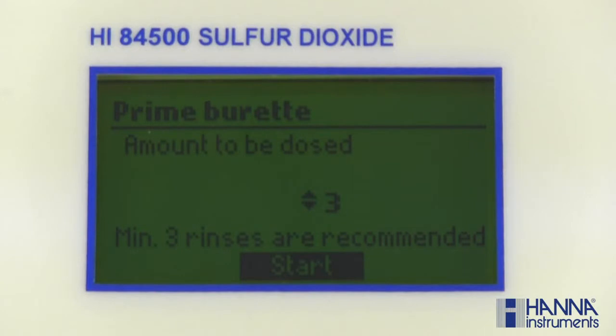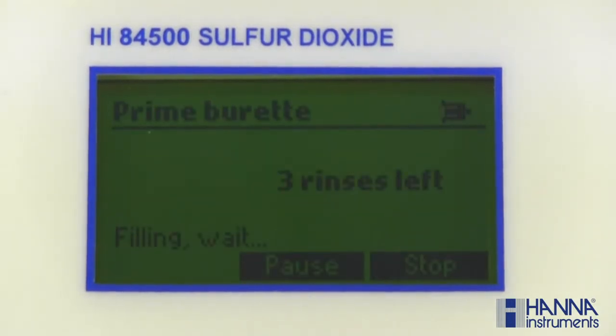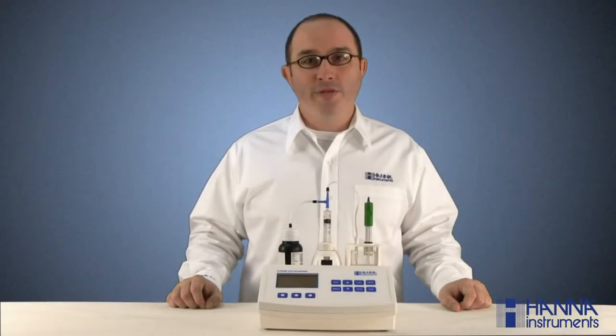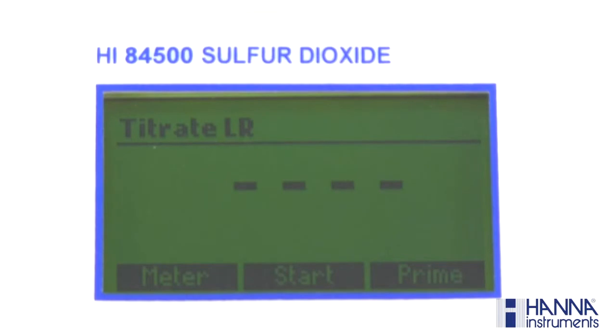Select the prime option from the titration mode. Adjust the number of rinses with the arrow keys and press start. The number of syringe rinses can be set between 1 and 5. The pump is now ready for calibration. A pump calibration must be performed every time the syringe, pump tube, titrant bottle, or ORP electrode is changed. It is also recommended to perform a calibration once per day.